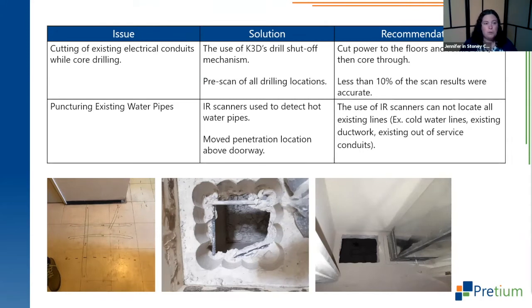We also ran into a few issues of puncturing existing water pipes in some walls, where we were penetrating our ducts from the units into the corridors. We did use IR scanners to try to detect hot water pipes in those locations, but found those scans don't necessarily locate everything. Things like cold water lines, existing ductwork, or out-of-service conduits don't necessarily show up when you scan.